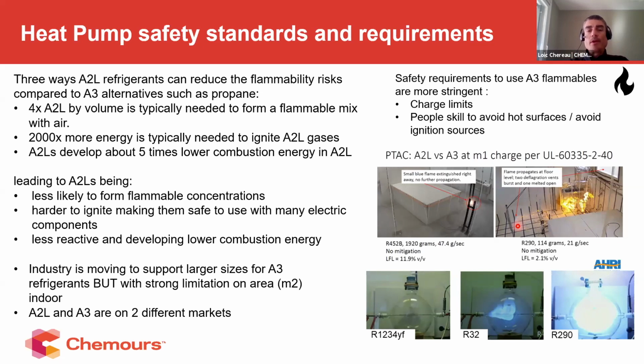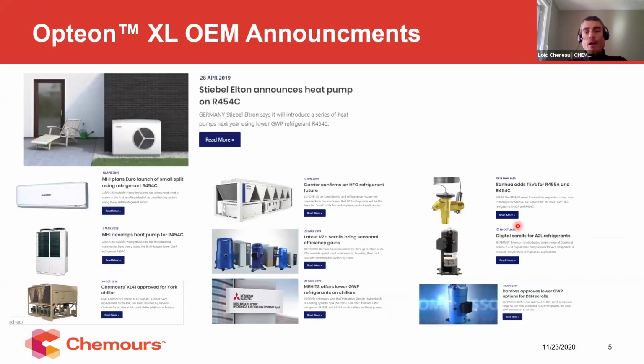And beyond that, it's not only the heating capacity limit that is seen and achievable with an A3. These systems are also developed for being used either outdoor or indoor, and there is a much larger proportion of A2L refrigerant use when we consider a heat pump to be used indoor. Very quick on that, because it's been also presented by Stiebel, but not only Stiebel, there is more and more adoption of HFO blends, the 454B, the 454C, be it for chillers or large heat pumps. And this is the clear trend we are seeing, to go to a lower GWP HFO.